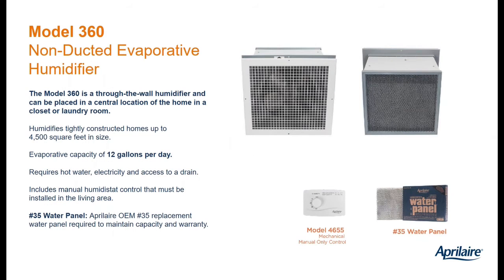The 360, same concept. You're going to run hot water to it, plug it in, run a drain line to it, but this is a through-the-wall unit. So you might pick, say, a bathroom closet, because bathrooms are a great place to get hot water to, power to, and a drain line to. And then on the other side of that closet, you would want that to share a wall with, again, a large open area, like a hallway. Air gets pulled in, humidified, and then pushed out that grill you see on the right, and then that air mixes and disperses throughout the house.